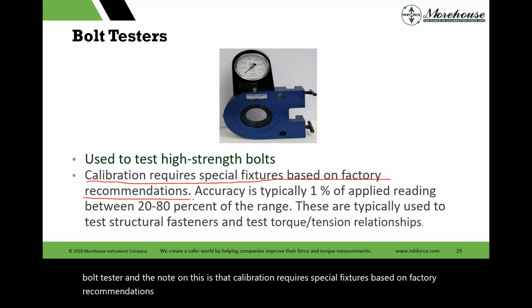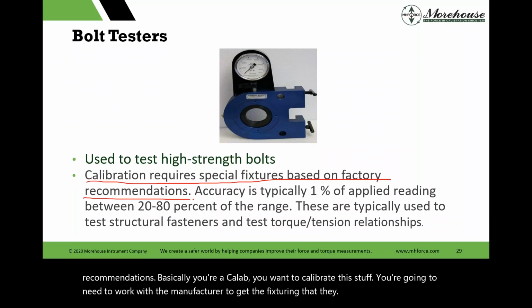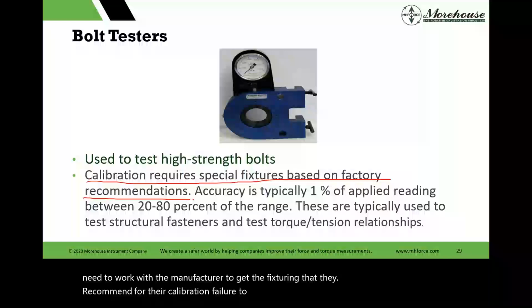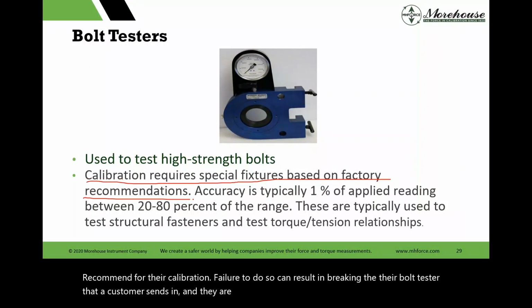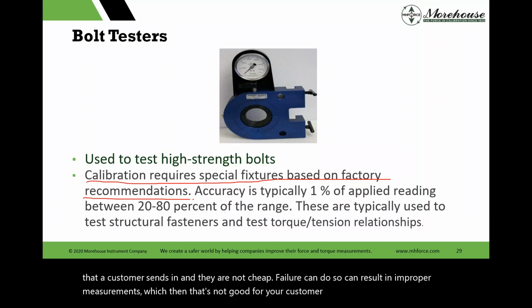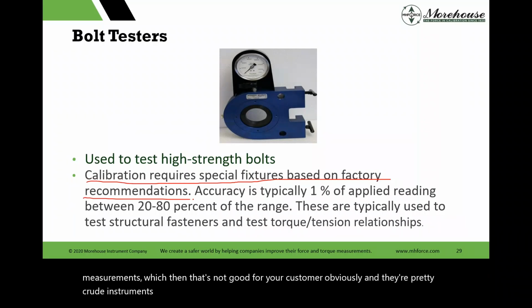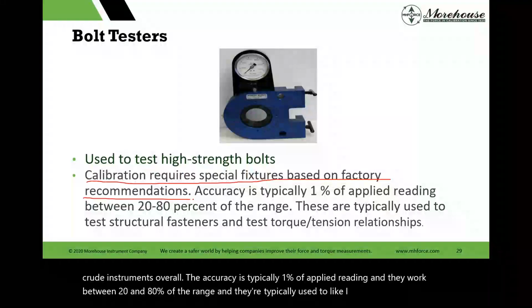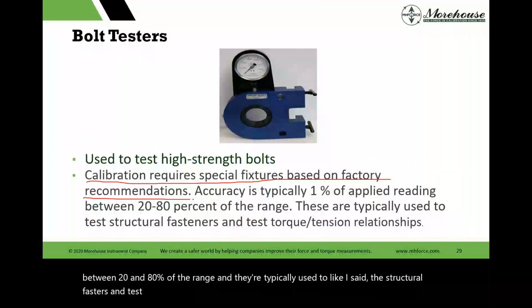Basically, if you're a cal lab and you want to calibrate this stuff, you're going to need to work with the manufacturer to get the fixturing that they recommend for their calibration. Failure to do so can result in breaking the bolt tester that a customer sends in, and they are not cheap. Failure can also result in improper measurements, which is not good for your customer, obviously. They're pretty crude instruments overall. The accuracy is typically 1% of applied reading, and they work between 20 and 80% of the range. They're typically used, like I said, for structural fasteners and to test torque-tension relationships.